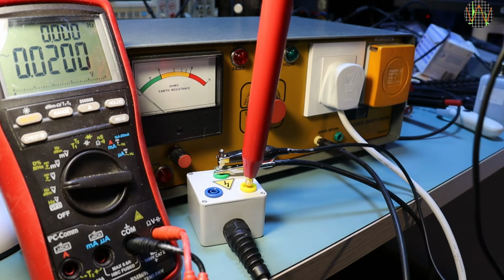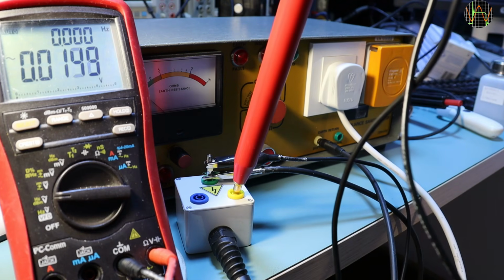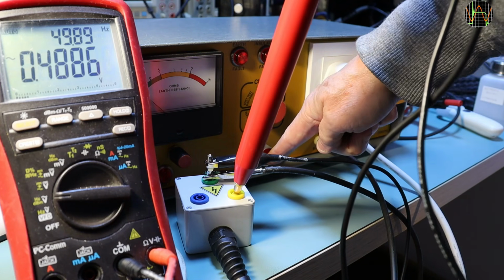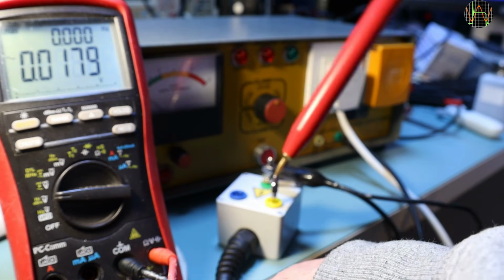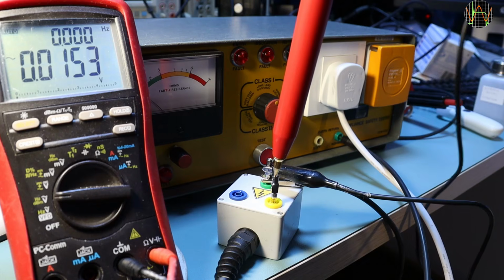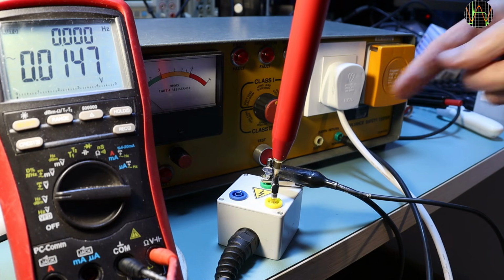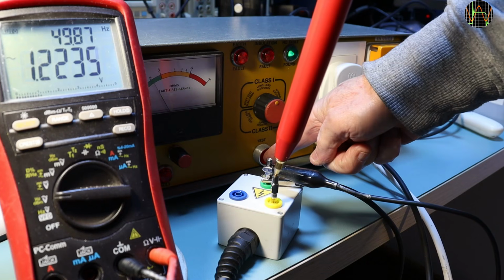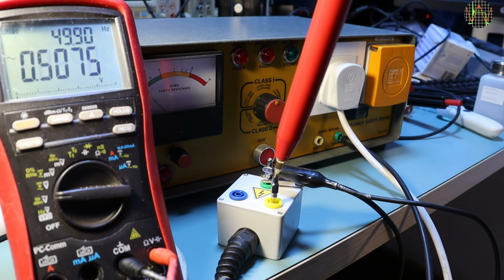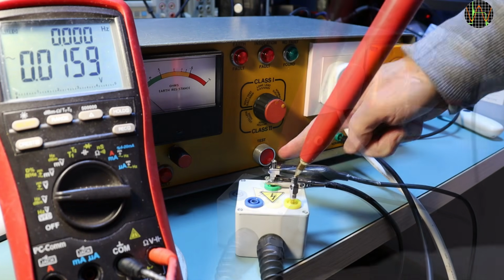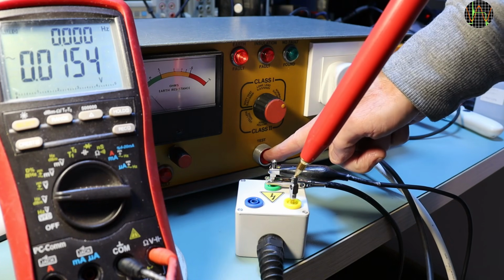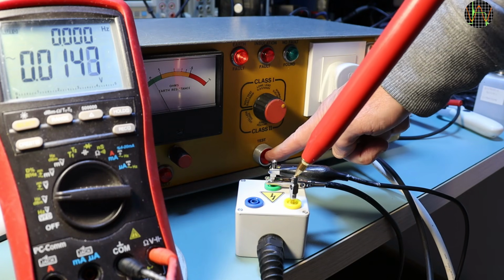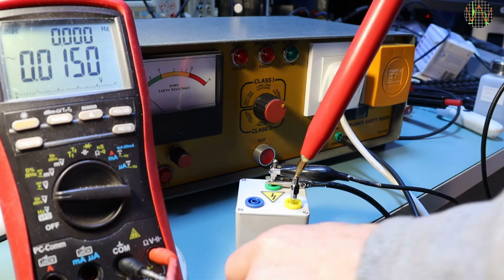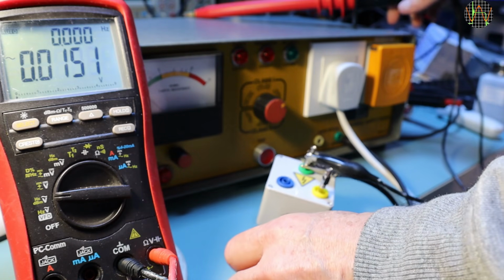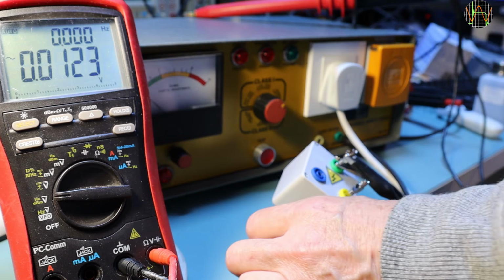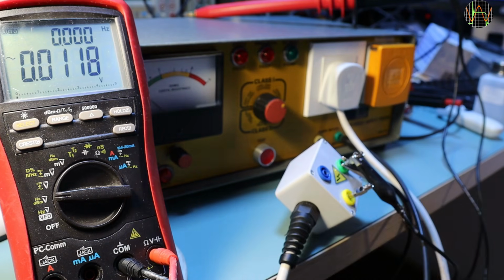Using class 1 soft settings, I should see about 500 volts, or 0.5 volts after the division by 1000, and indeed that's about what's there. How about the long lead setting? I added a banana plug tip into the live socket to make probing a bit easier. Okay, we should see 1250 volts and it shows 1224, not bad. Onwards to normal setting, and nothing. Because we still have the earth fault, that shouldn't be there. At least now I know that the unit first tests for earth faults, and if that fails, it does not proceed to insulation testing, which is very sensible given the safety implications.